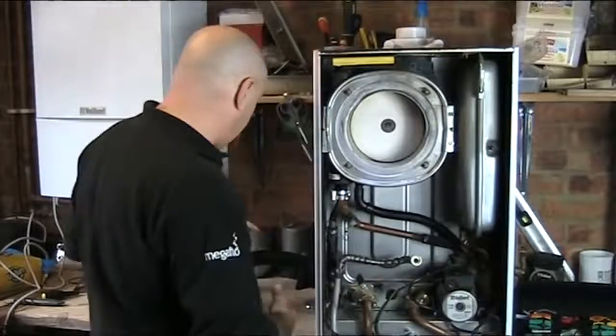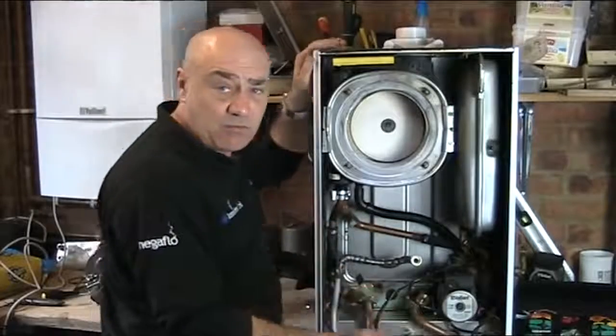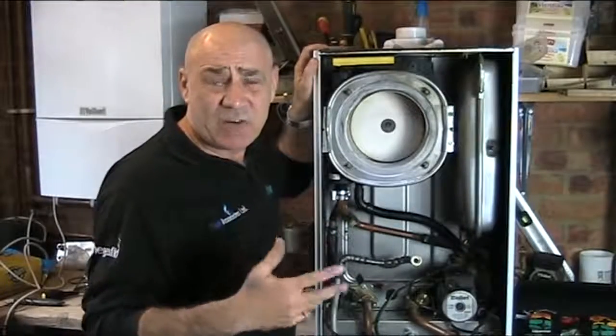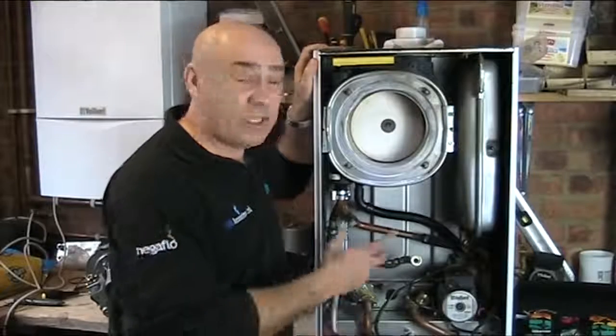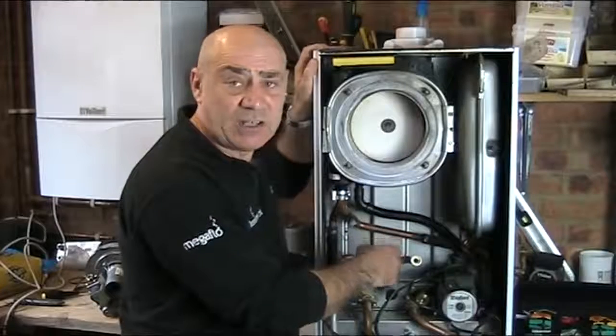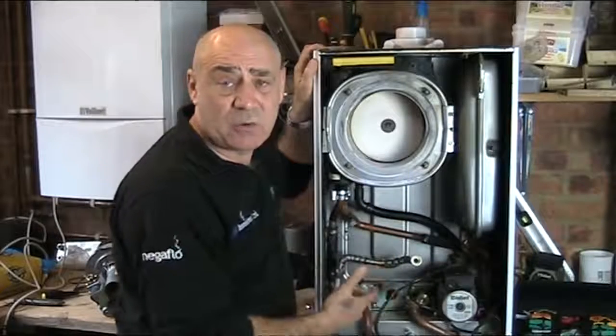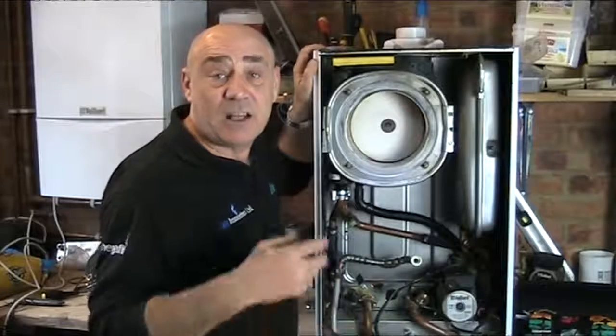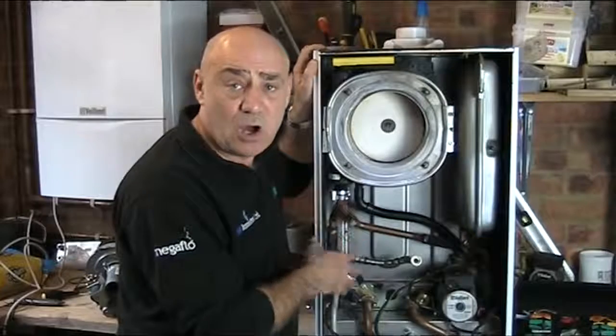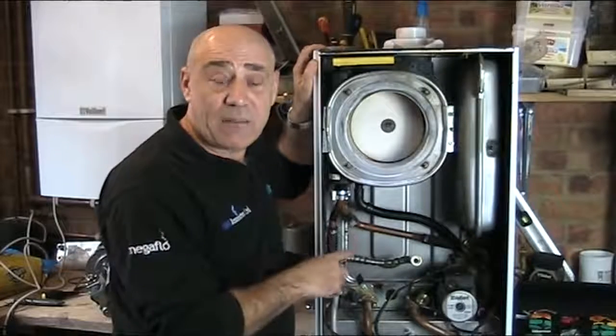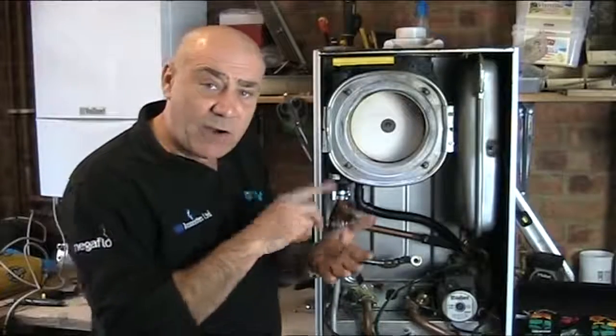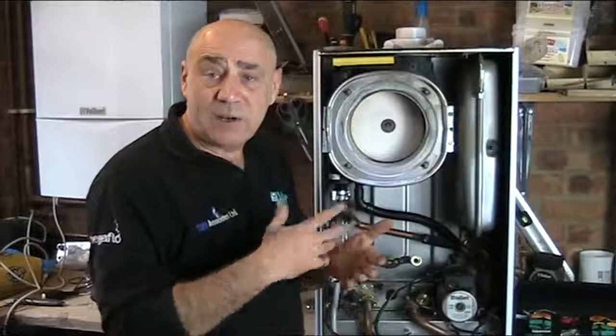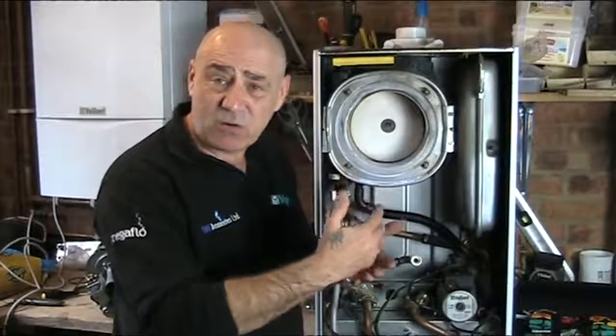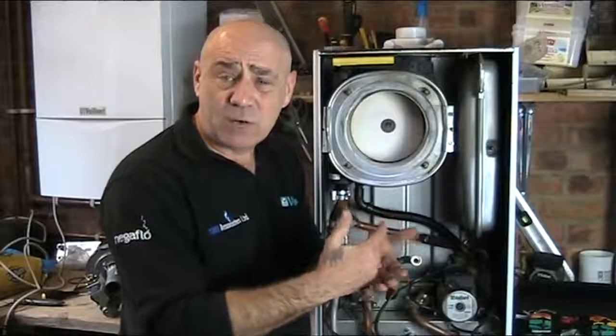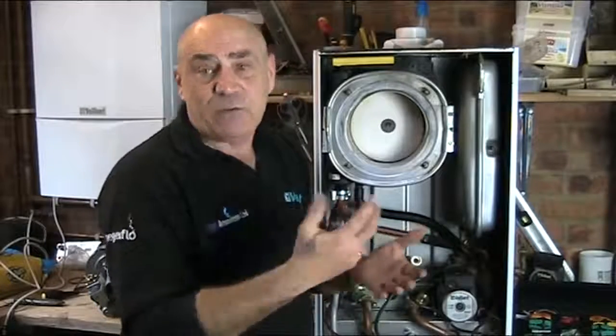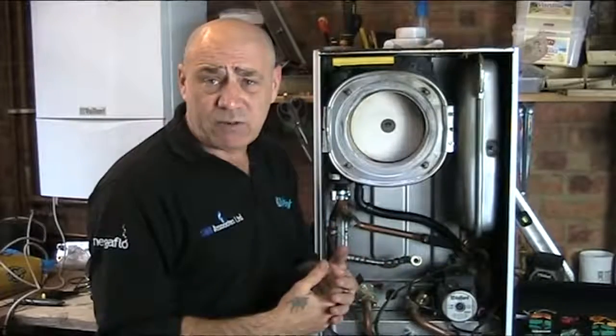Once we've done all that, we will then rebuild the boiler, refill the boiler, and then put it into what's called a P0 test program, which is an engineer's program that we use to purge and clear the heat exchanger and the domestic heat exchanger and the internal circuitry of the boiler to make sure there's no air trapped in there and that we can't damage the boiler by firing it up too early. While that program's running, we will be busily tapping away on our iPads because we will be filling out your printed and PDF service record, which lists all the criteria that has been carried out, and it will give you all the notes as to what's been done, and if you need any replacement parts, it will all be on the service record.